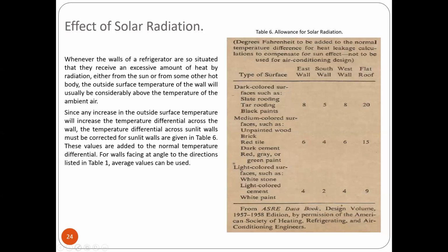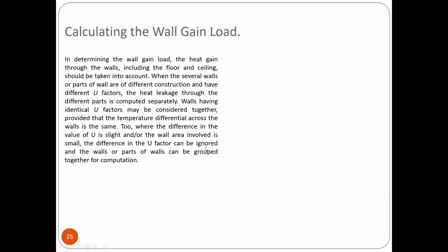Now, calculating the wall gain. In determining the wall gain load, the heat gain through the walls, including the floor and ceiling, should be taken into account. When the several walls or parts of walls are of different construction and have different U factor, the heat leakage through the different parts is computed separately. Walls having identical U factors may be considered together, provided that the temperature differential across the walls is the same. So too, where the difference in the value of U is slight and or the wall area is small, the difference in U factor can be ignored and the walls or parts of the wall can be grouped together for computation.